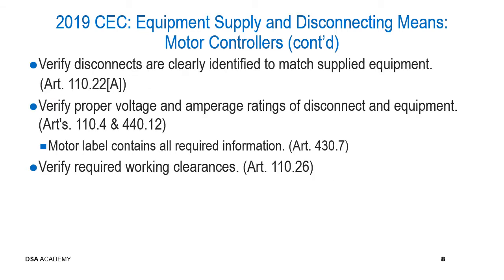Some of the duties that a project inspector would apply with respect to verifying motor disconnects are, number one, verify that the disconnects are clearly identified to match the supplied equipment. This requirement comes from Article 110.22(a). Also, verify proper voltage and amperage ratings of the disconnect and the equipment. So you want to make sure that the volt and ampere ratings of the disconnect and the equipment match. This is required per Articles 110.4 and 440.12.